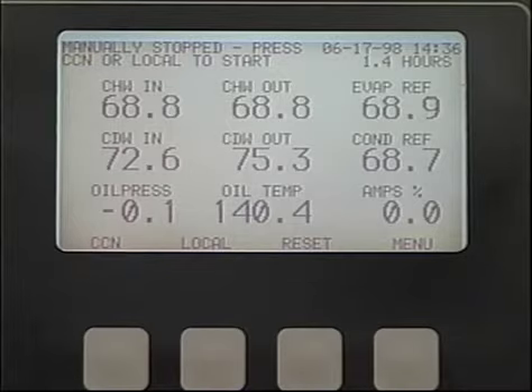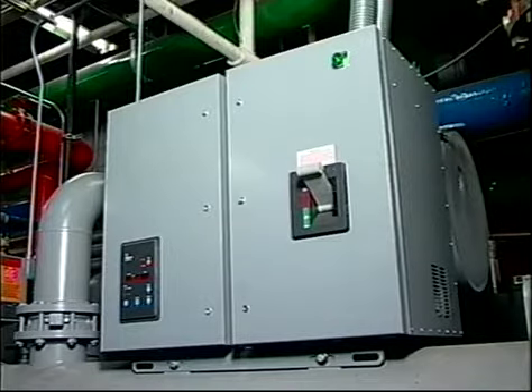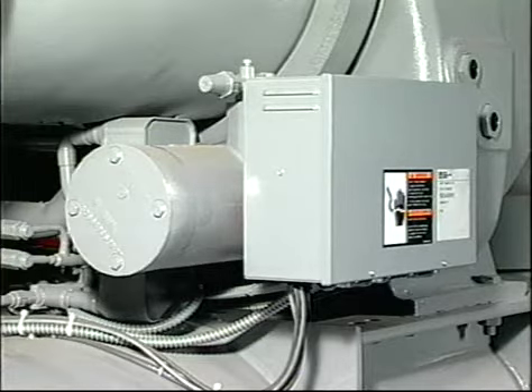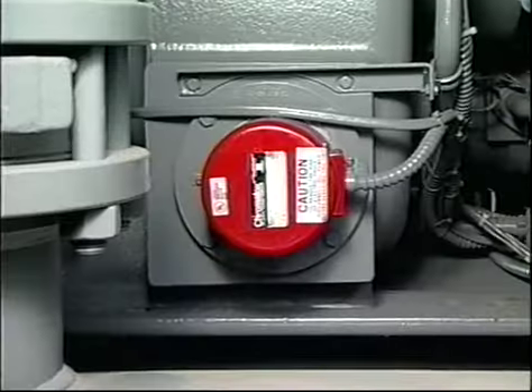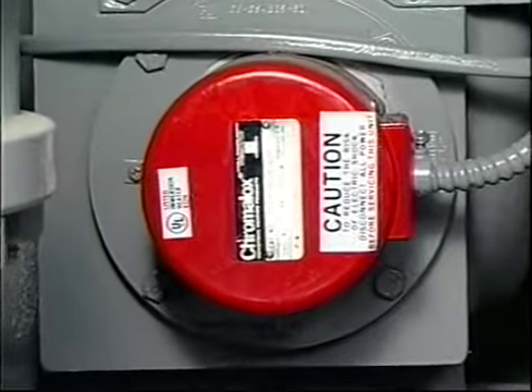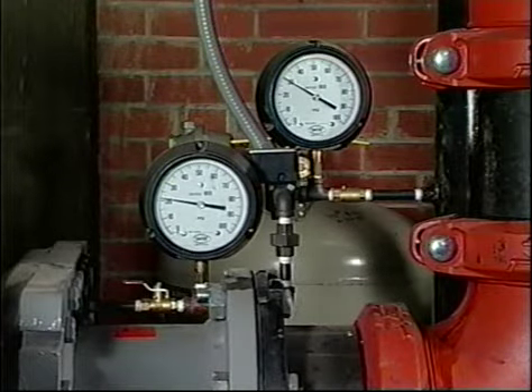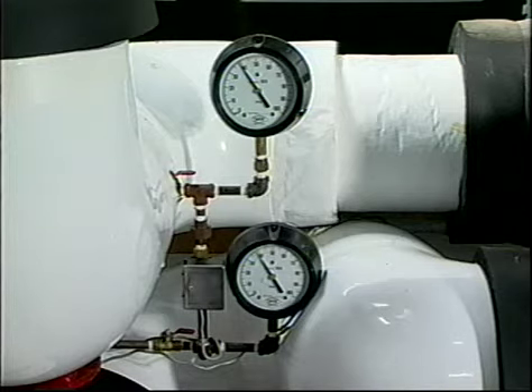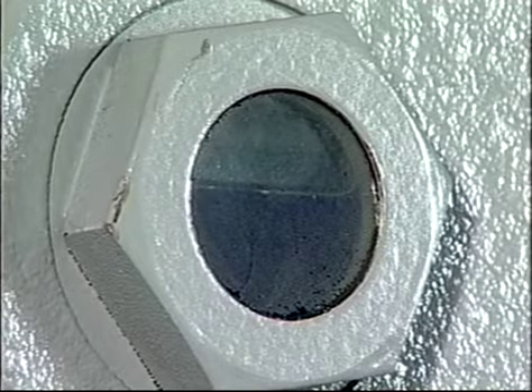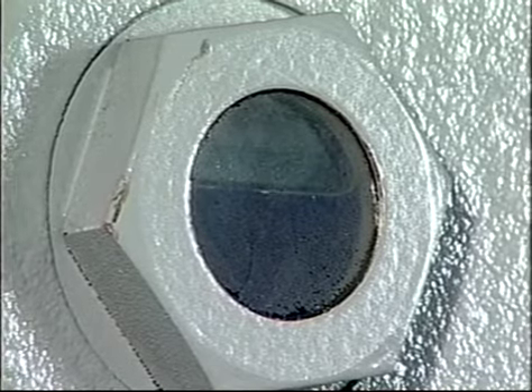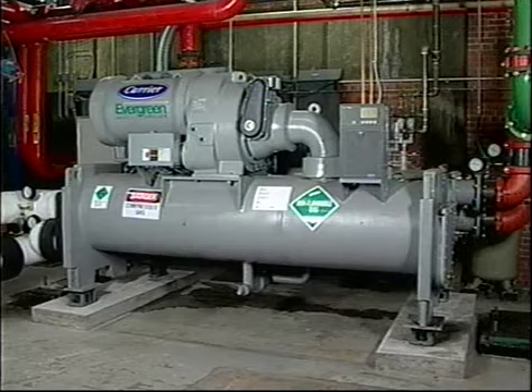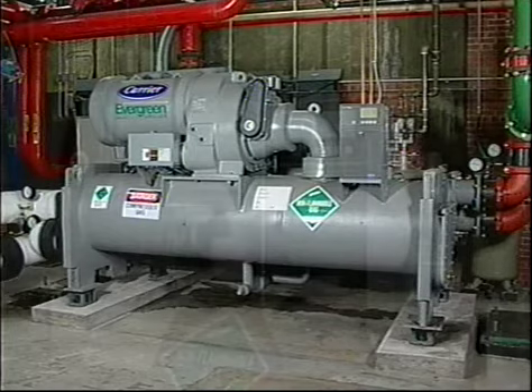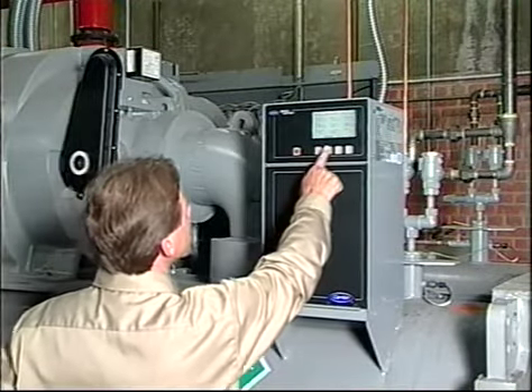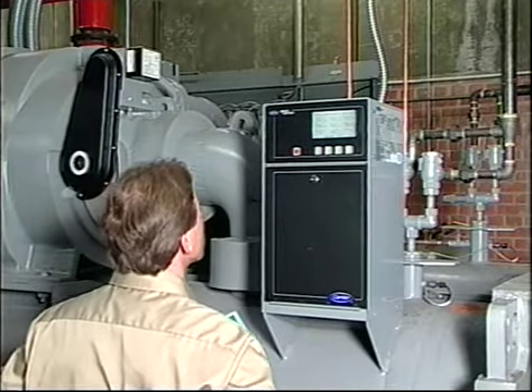There are several things that need checking before you push the start key, either local or CCN, to start the machine. Is power turned on to the main starter, the oil pump starter, the water pumps, the tower fans, the oil heater and machine controls? Has proper water flow in the cooling tower circuit been confirmed? Has the chilled water circuit been checked out for proper flow? Is there oil in the compressor oil reservoir sight glass? Whether the machine is on or off, you should always see oil there. For our example, we will assume your chiller is a standalone installation subject only to local control. Depressing the local key allows the chiller to start, run, and shut down in response to commands from the control system supplied with your chiller.